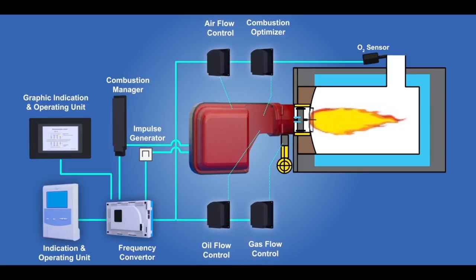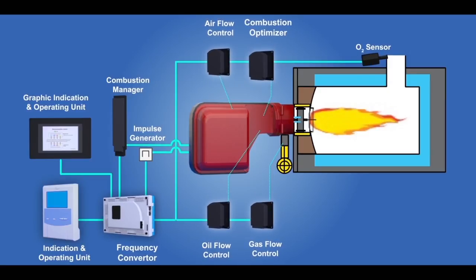Designed to electronically maintain the accurate air to fuel ratio, ECR is an advanced supervisory control system and fail-safe BMS with built-in diagnostics. O2 trimming and blower motor speed control can achieve better efficiency even on part load.